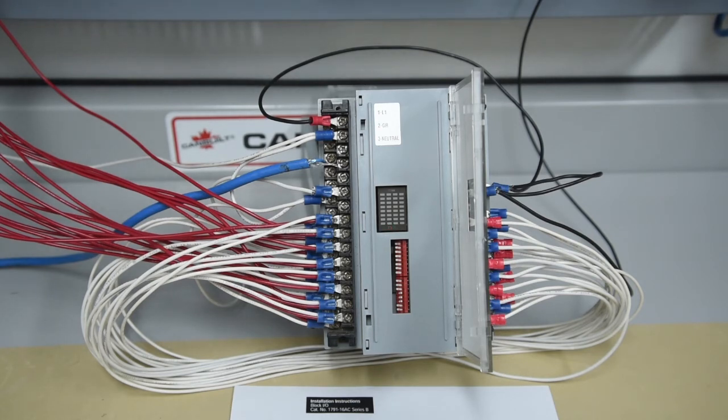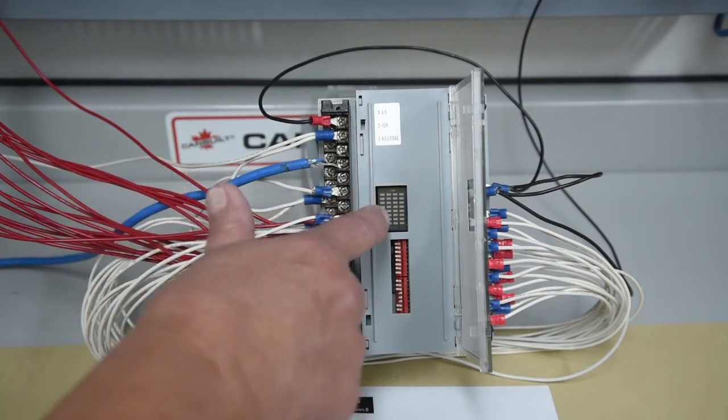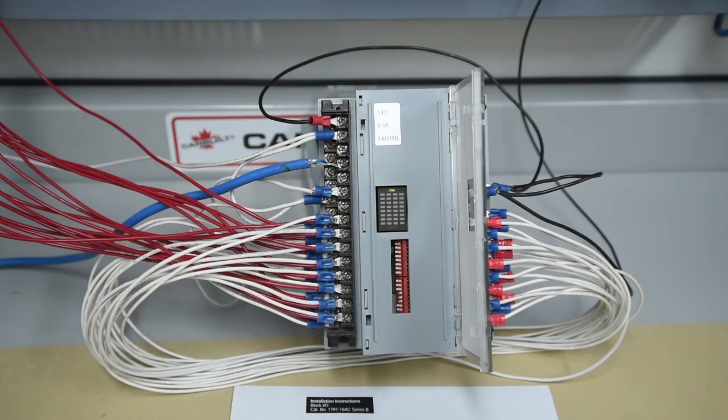The only way to get that so it communicates again is now you have to put the PLC into program. Go into your channel configuration. And in this case, this is channel 1B. Change it to match that remote I.O. Apply it. And you can see how it's now, as soon as I applied it, it's flashing green. So it's ready to go. Put it back into run mode.